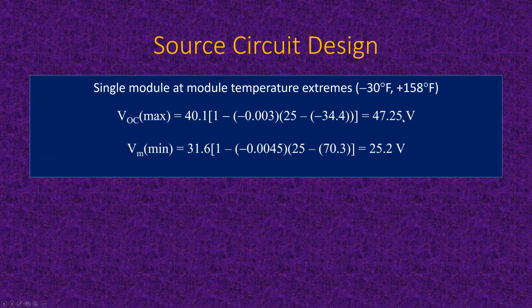All right, and then for the maximum power voltage, that's the voltage where the solar array delivers maximum power. That voltage goes down as the array gets hot. And we're saying the maximum temperature might be 158 degrees, which is 70.3 degrees Celsius. So it starts out at 31.6, but by the time it gets up to 158, it drops down to 25.2. So you've got to make sure you've got enough there. Oftentimes you can't track maximum power for less than a certain value. And so this is useful.